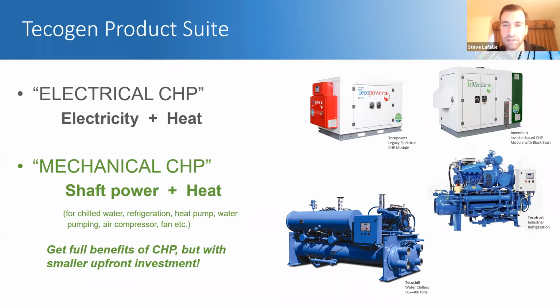So that engine is consuming natural gas, producing shaft work that's turning a process, in this case the vapor compression cycle, to make chill water. And then we recover all the waste heat from that prime mover, from that engine, from the exhaust gases, the engine jacket, the engine oil, and deliver that to the customer for free for things like reheat, domestic hot water generation, process heat, what have you. That heat is all a free byproduct of that process. It's not condenser heat, we're not raising the condensing temperature to try to get useful heat. So it's a little bit different than a heat recovery electric chiller.